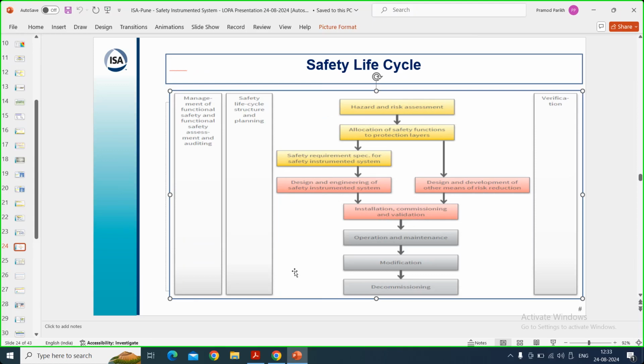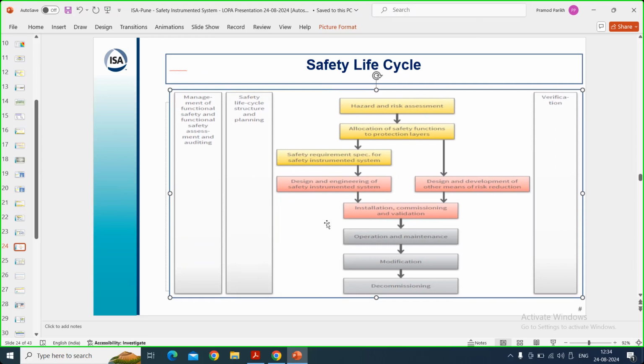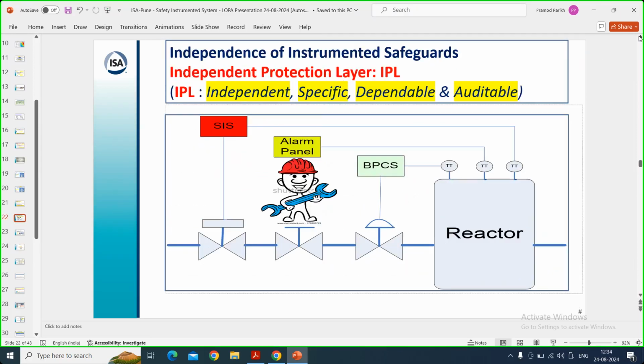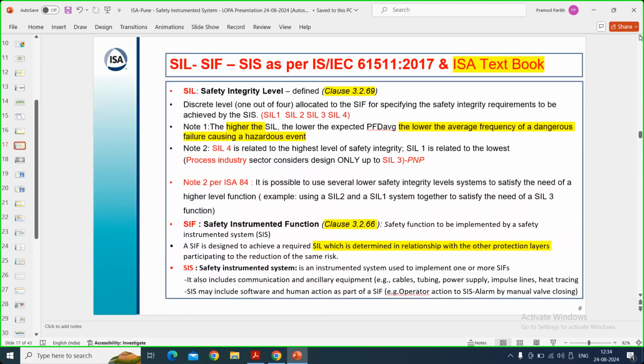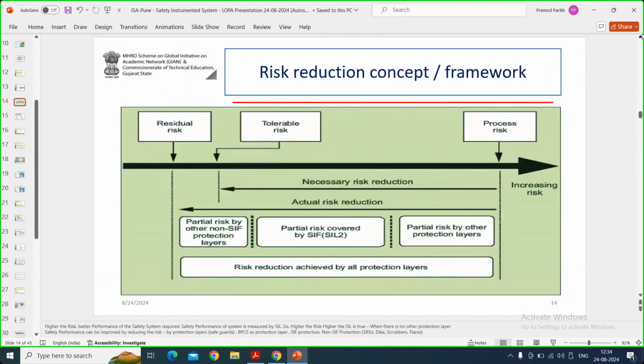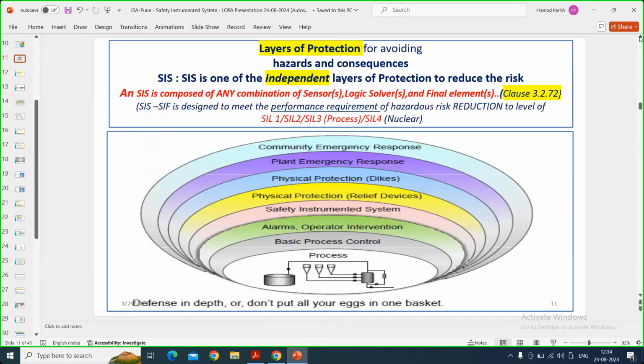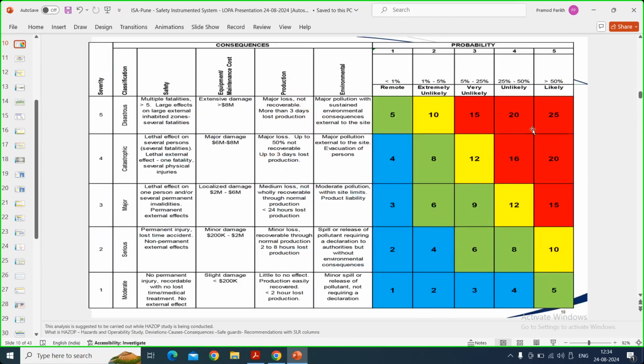I would say that SIL level is about whether you have designed your plant to the required SIL level or not. That is important. What is the level of risk? SIL level is not to be reached due to aging, but SIL level is to be decided based on your hazards. If you are having a high hazard, and the likelihood of that hazard happening is very high, then you have to design your system so that your risk is addressed.